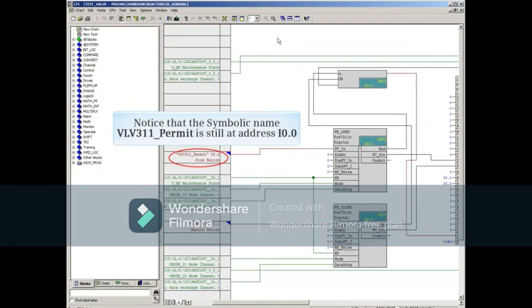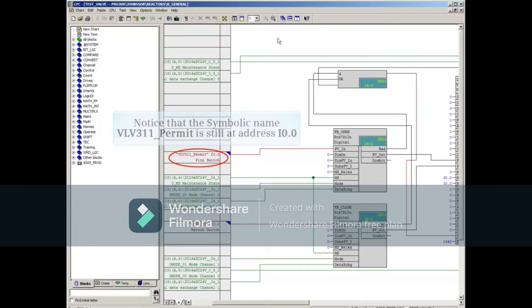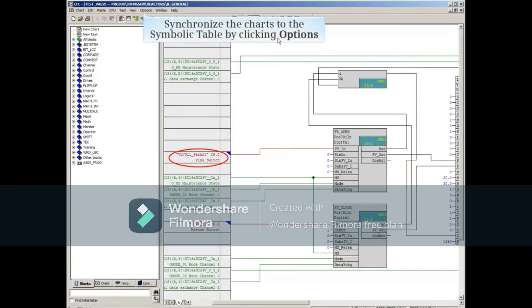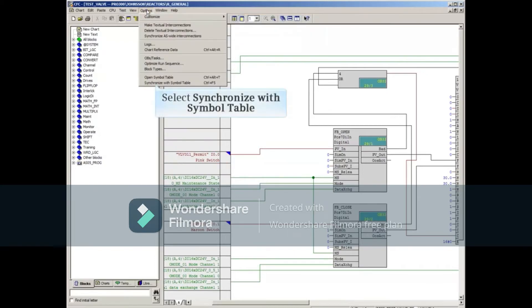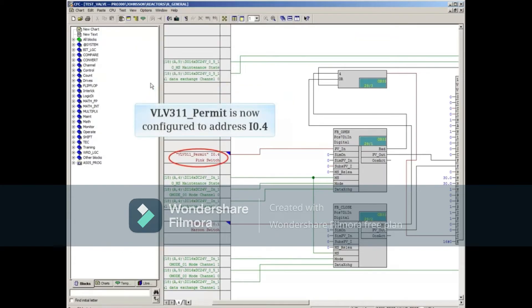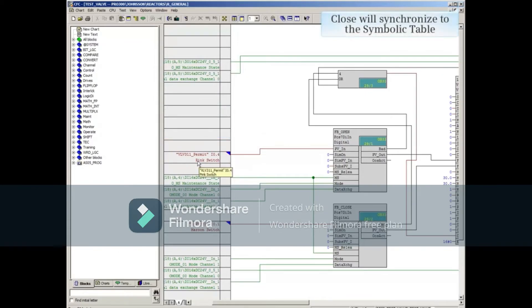Notice that the symbolic name VLV311 underscore Permit is still at address input 0.0. You can now synchronize the charts to the symbolic table by clicking the Options menu, and selecting Synchronize with Symbol Table. Notice that the VLV311 underscore Permit symbol is now configured to address input 0.4. Synchronization of the charts to the symbolic table will also happen when the CFC Editor is closed.